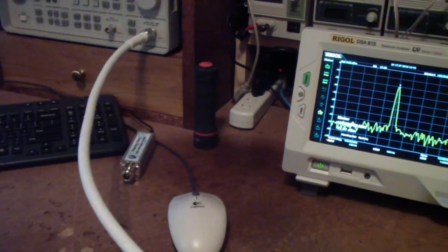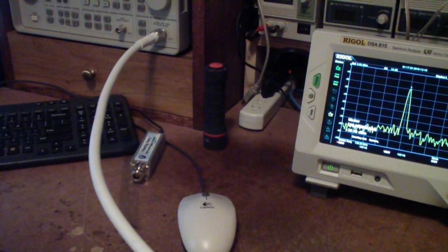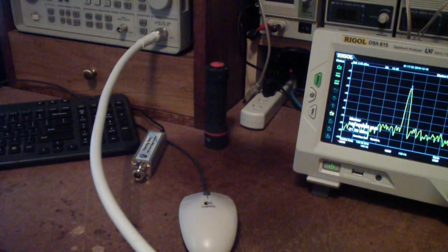15 dBm. Now, frankly, this varies over the frequency range. For example, if I go to 1 gigahertz, instead of minus 20, it shows minus 12 dBm. And so what I have to conclude is that, at least with this particular version, the copy that I have of the Triarchy vector signal generator, which is right there, I can't depend on the output level settings that show in the software. You have to actually measure the output.